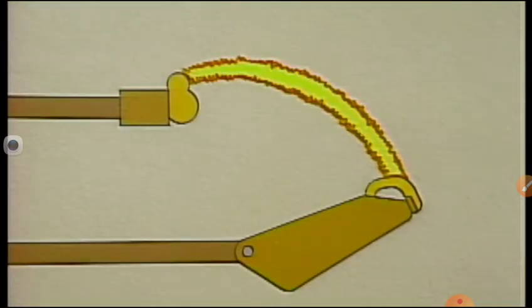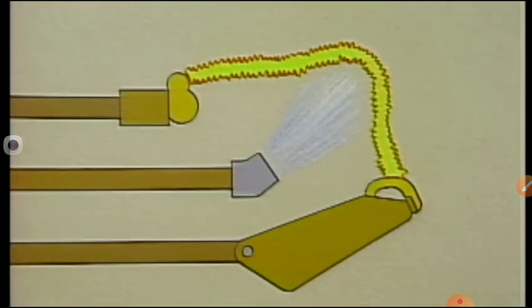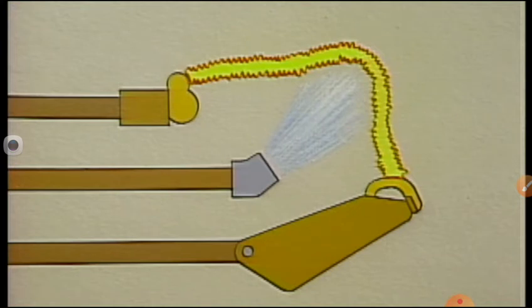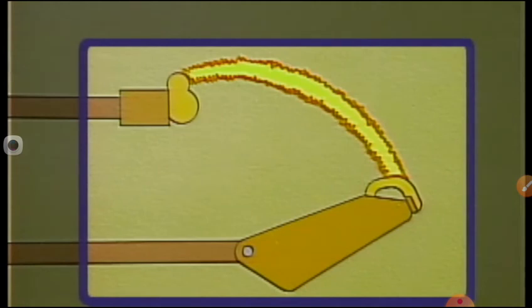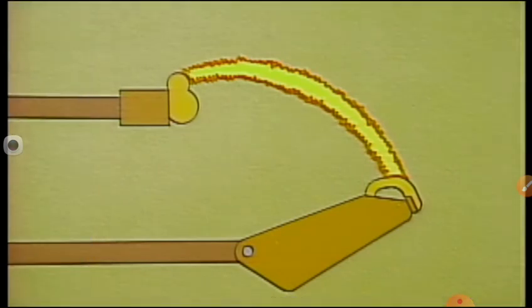Cooling refers to any physical effects that take heat away from the arc. In general, when air and gases are heated, they become conductive. The surrounding air will absorb the heat inside the arc, so breakers are designed to take heat away from the arc. Some common ways that an arc is cooled in a breaker include directing a blast of air or gas at the arc, forcing the arc against cold metal or lengthening it, and submerging the breaker contacts and the arc in insulating oil, which absorbs and dissipates the heat.